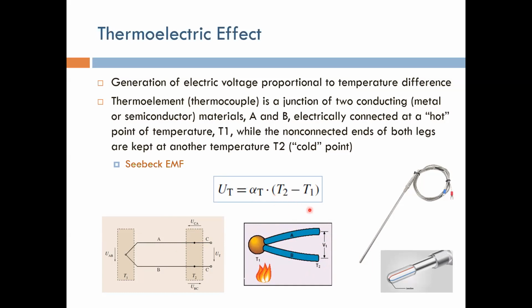So what you get is a relative measurement, not an absolute one. You can't measure the voltage directly to get an absolute temperature; you measure temperature relative to a reference temperature. To measure this temperature, you have to measure another reference temperature, using another temperature sensor — not another thermocouple — at that reference point.